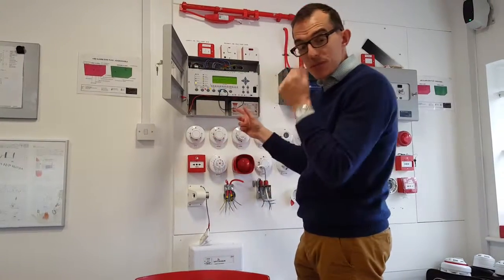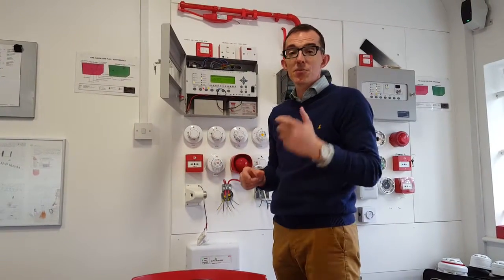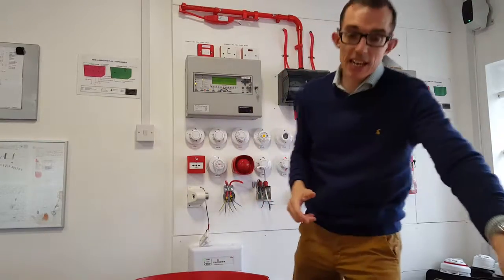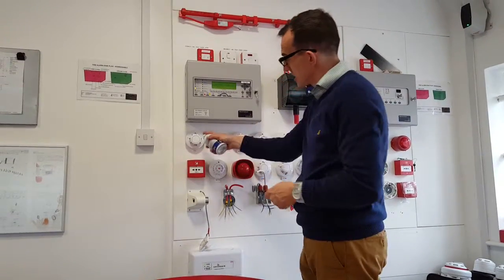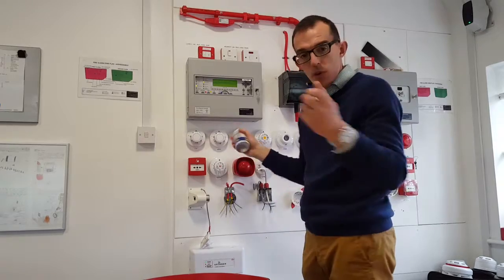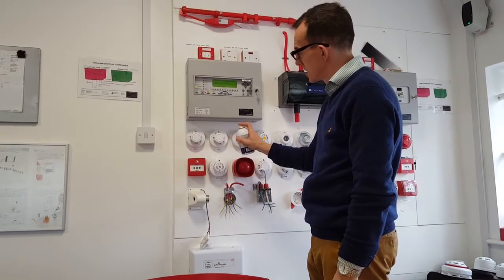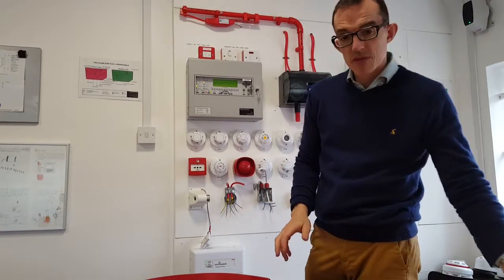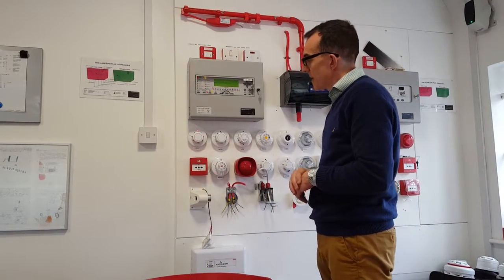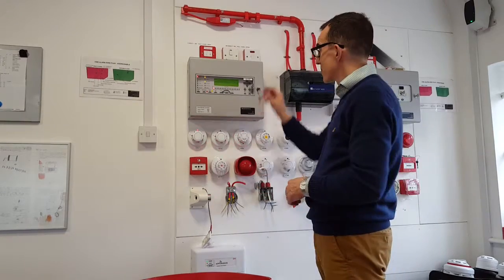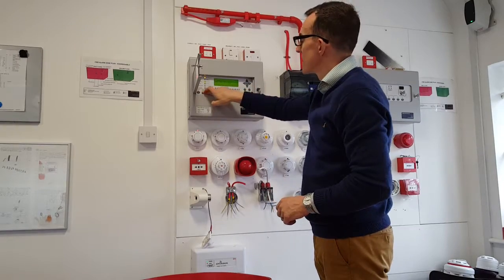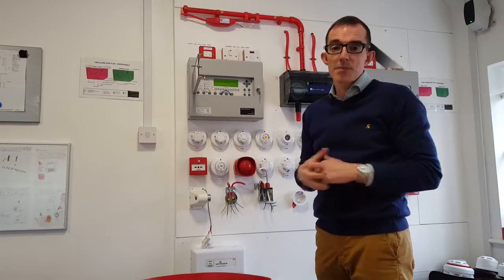When you're testing the fire alarm system, the purpose of the test is to prove that it would do what it was supposed to do in the event of a fire. For example, if I get a can of artificial smoke and test this detector here, some noises may start going off and the beacons may start flashing now. So just a few cans of smoke in a few places, then the panel goes off, and it does what it's supposed to do.